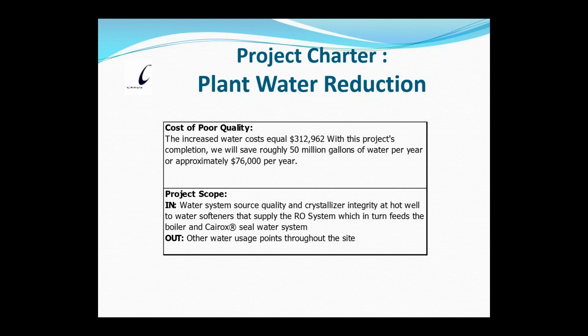The project scope is the water system source quality and crystallizer integrity at the hot well to water softeners that supply the RO system, which in turn feeds the boiler and the Cairox seal water system. Out of scope, something we didn't look at all, was other water usage points throughout the site. Like I said, this is phase 1. Towards the end of the slideshow, I will present my next 2 phases of the water reduction plan that we're currently working on.